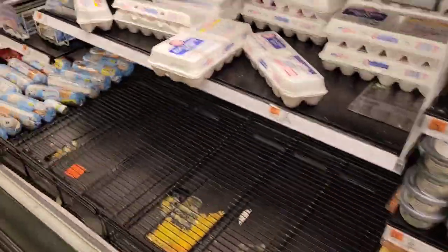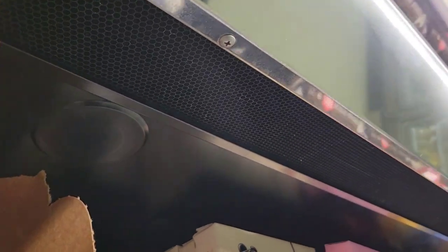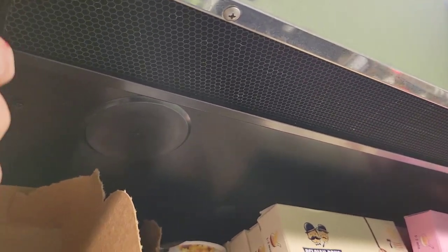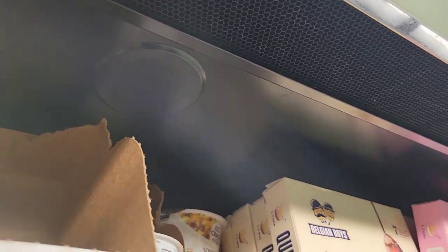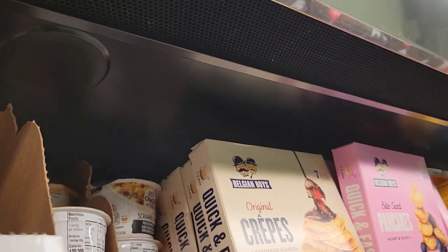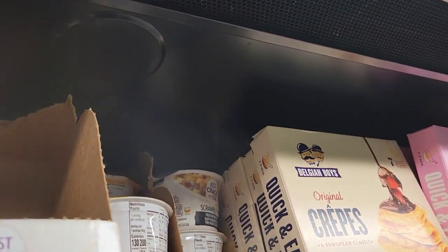So the fan right there was okay. So now I'm gonna come over here. I'm just gonna make sure the honeycomb isn't plugged. Now I have a video out there where I found a plugged honeycomb. You can take a look. But on these medium temp cases, plugged honeycombs are super duper common.